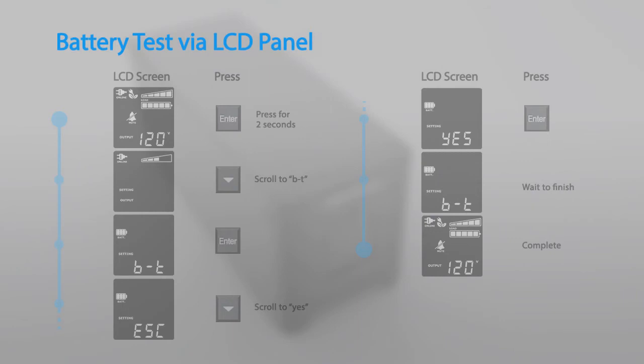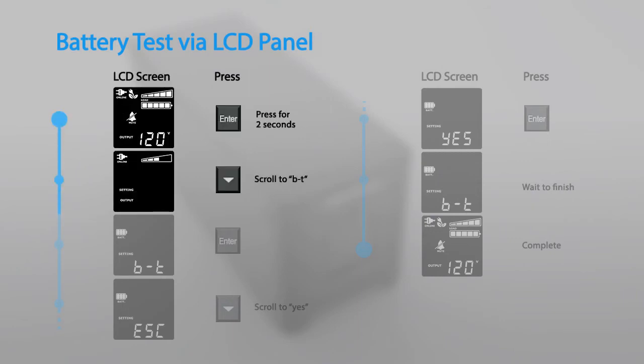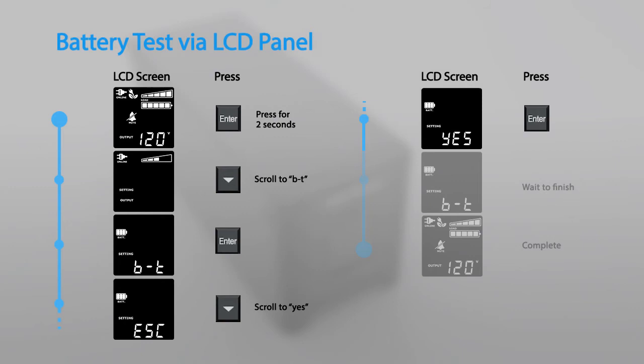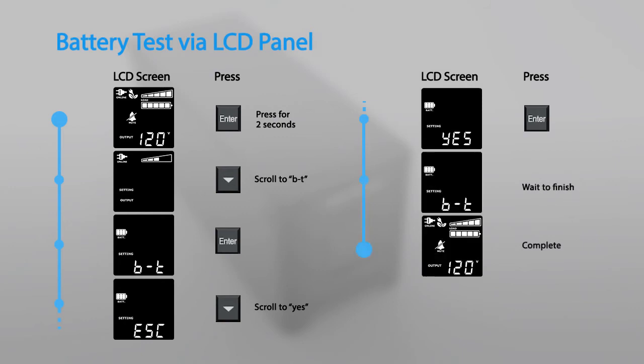To perform battery test via the LCD panel, hold down the enter button for two seconds to access the configuration menu. Select the BT option and select yes to perform the battery test. The test will run for five seconds and then return to normal operation.